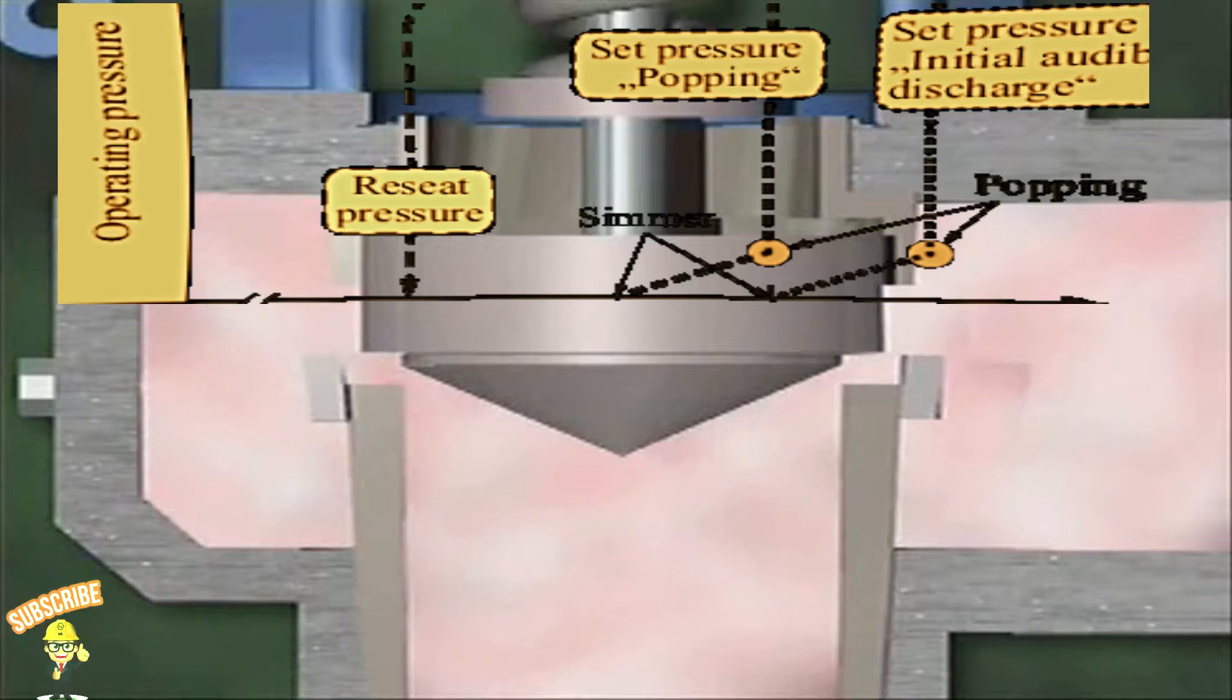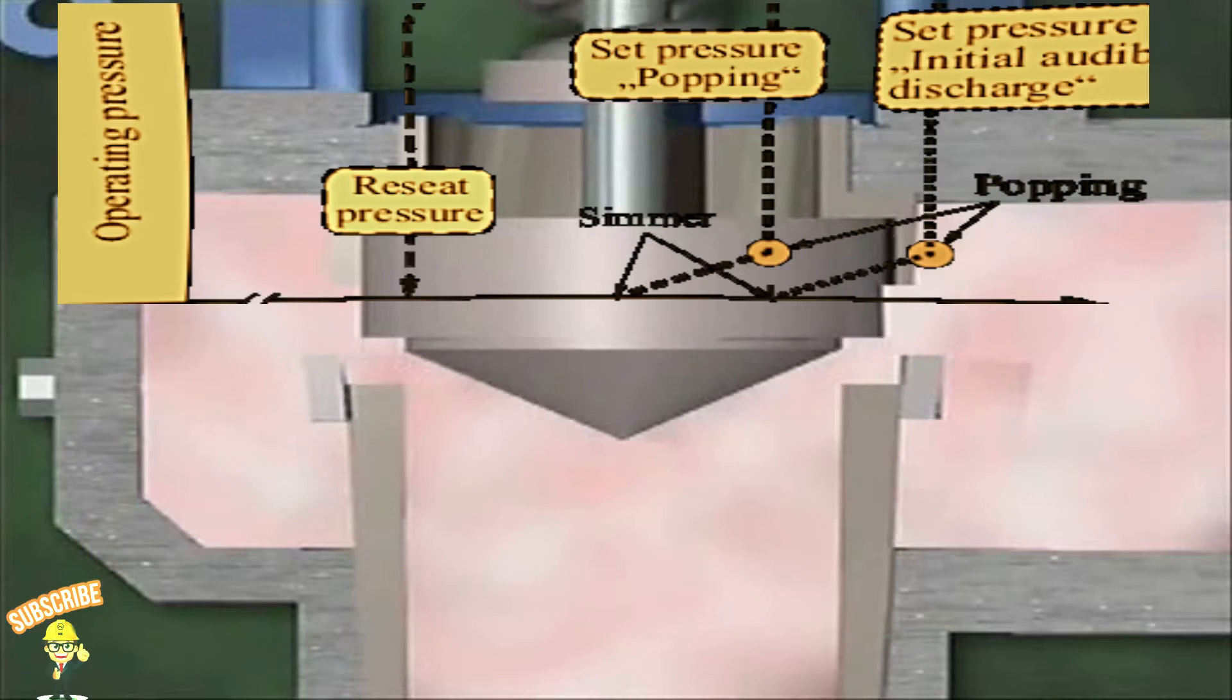If the pressure in the system continues to increase, the velocity of the escaping fluid will also increase, causing the disc to gradually lift higher until it reaches the fully open position. Since the initial opening of the safety valve is about 60%, a large volume of fluid is allowed to escape quickly.